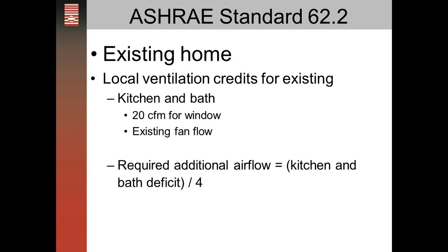To figure the additional airflow required continuously, you take the deficit from the kitchen or bath and divide that by four. In our example, a 60 CFM kitchen fan plus an operable window equals 80 CFM, leaving a 20 CFM deficit. For the bath, 30 CFM flow plus an operable window equals 50 CFM, which is sufficient. So we just have the 20 CFM kitchen deficit, divided by four, giving us 5 additional CFM continuous to add to our ventilation rate.